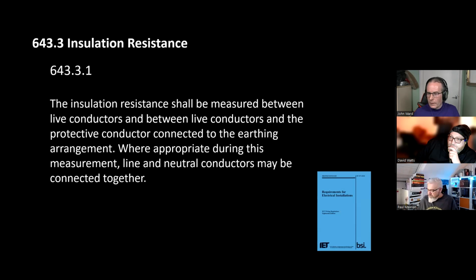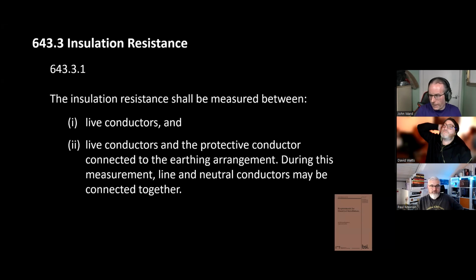John, IR. Yep, insulation resistance. This is what the Blue Book used to say: measuring it between live conductors and between live conductors and the protective conductor while it's connected to the earthing arrangement, and where appropriate, line and neutral conductors may be connected together. And now in the new Brown Book, insulation resistance shall be measured between live conductors and the protective conductor connected to the earthing arrangement. During this measurement, line and neutral conductors may be connected together. Pretty much the same thing reformatted.